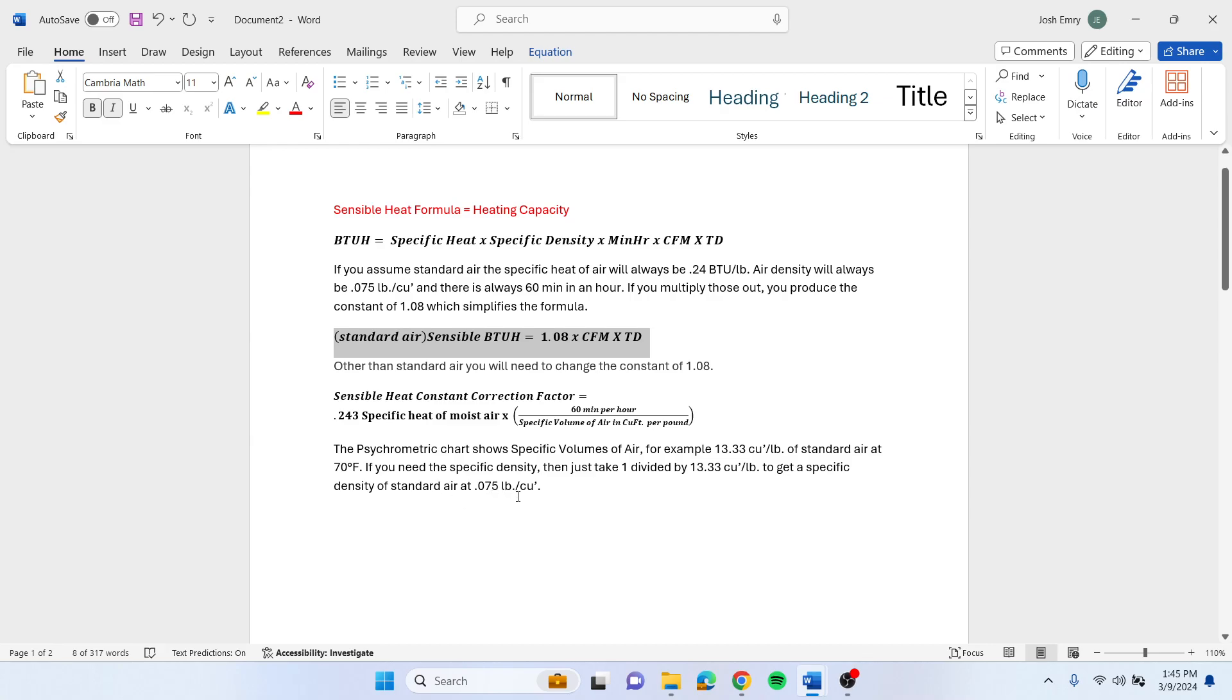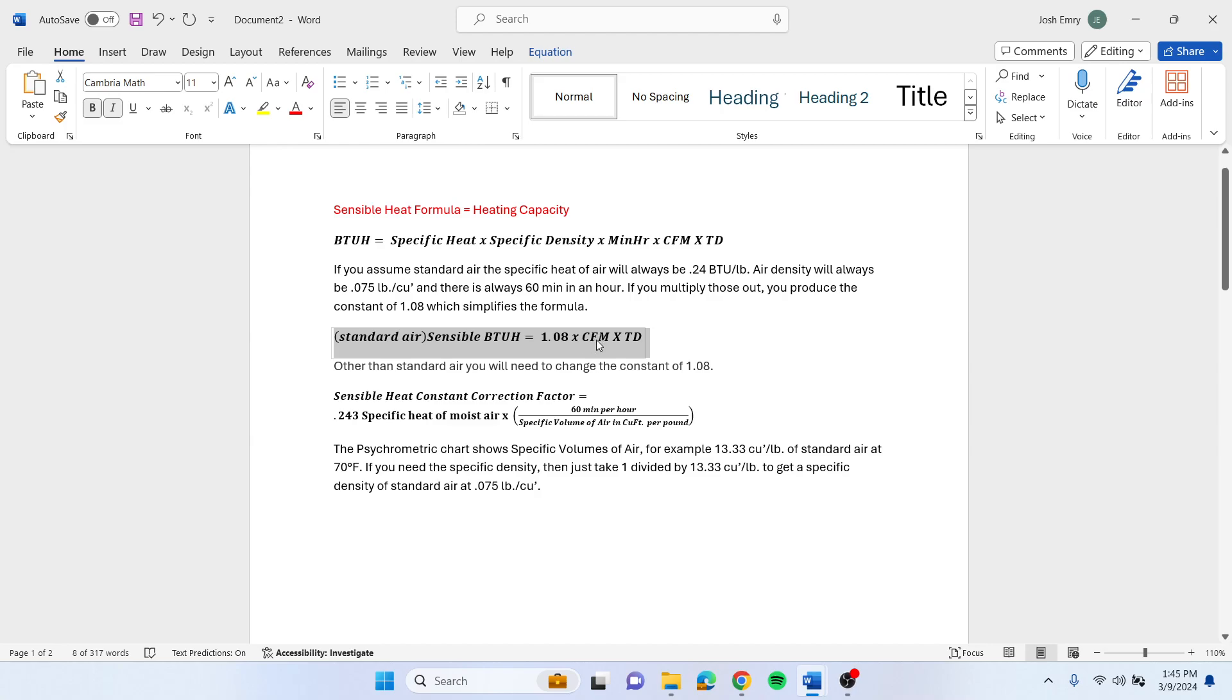That's how you can change it. Then you just take your 1.08, or if you have a correction factor, then you take that, your new correction factor, times your CFM that you've read, times your temperature difference, and that will tell you what your actual BTUs are of that unit or coil.